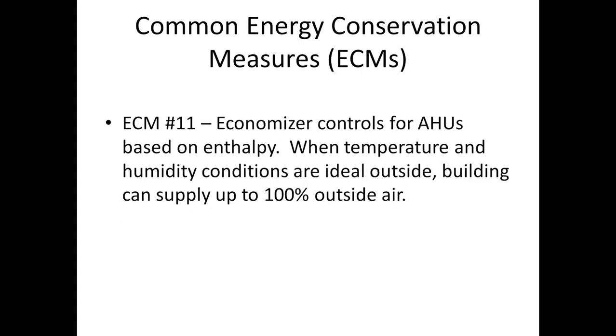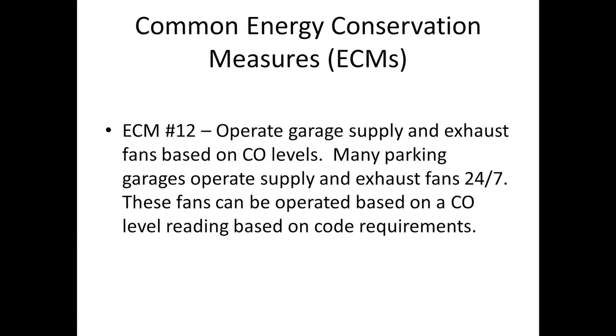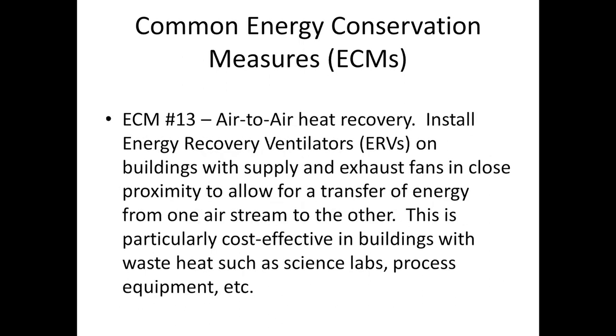Essentially looking at what the enthalpy is, so the temperature and humidity of outside air, and when it's cost effective and advisable for the building, bringing in that outside air as opposed to heating or cooling outside air. Operating garage supply and exhaust fans, these are almost always left on 24/7, but installing CO level monitors allow us to turn those supply and exhaust fans on and off based on carbon monoxide concentrations built up in the parking garage. We have air-to-air heat recovery.